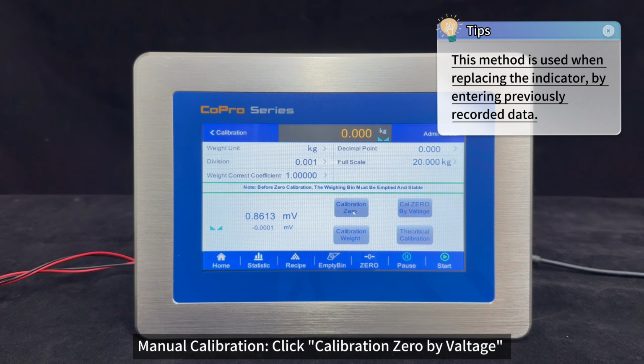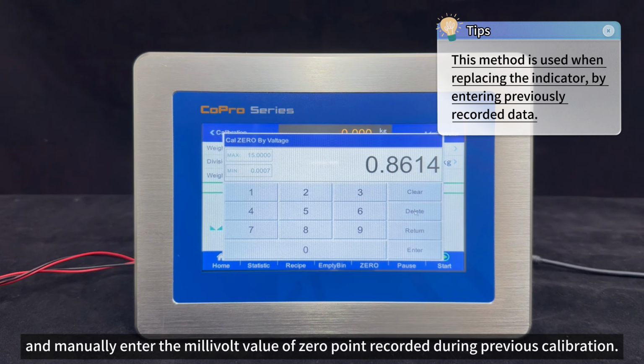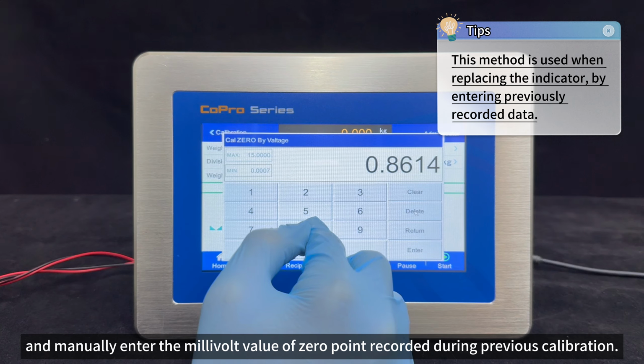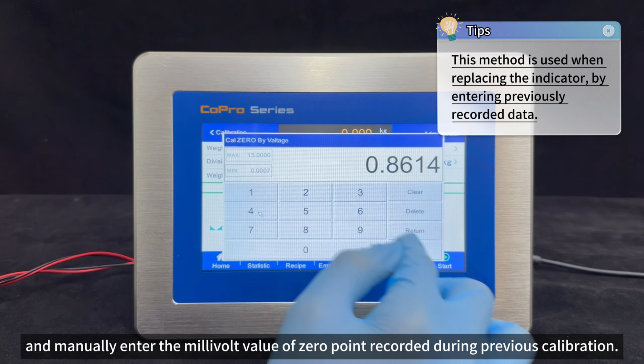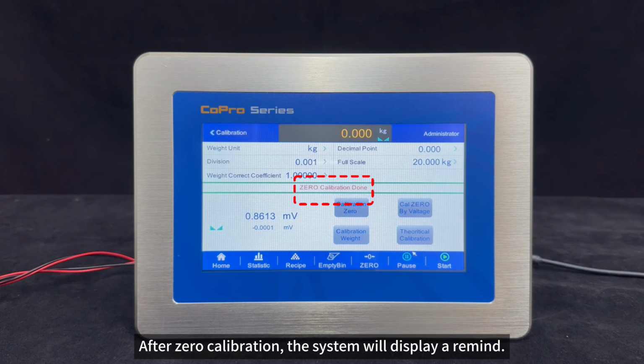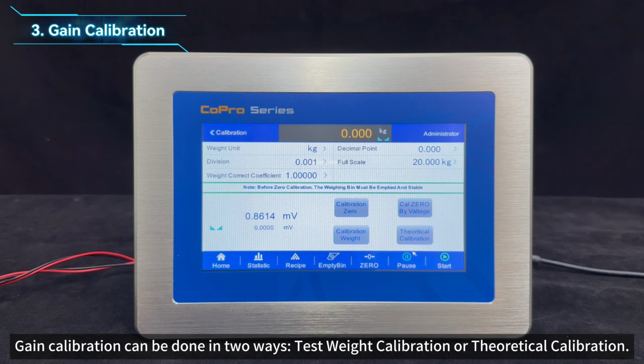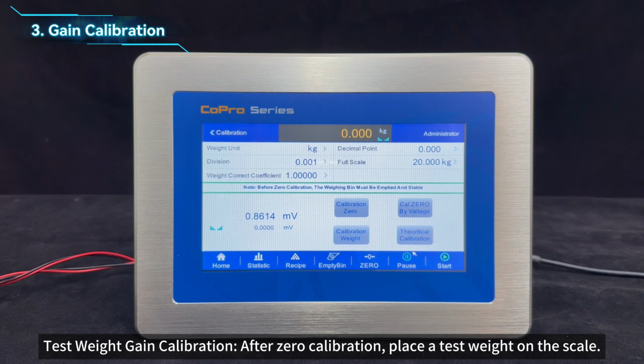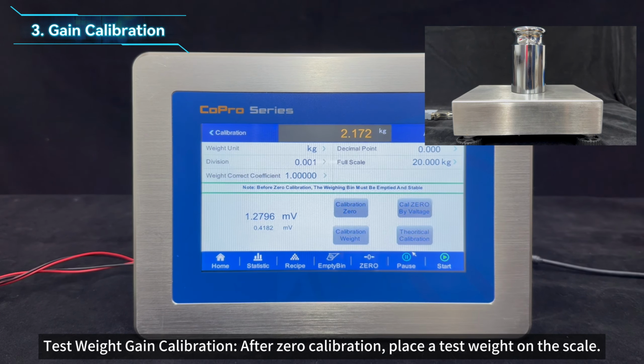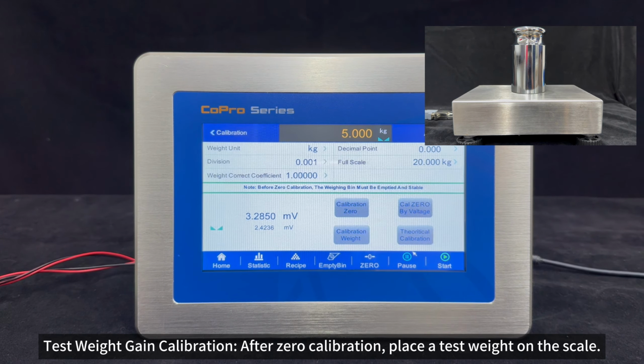Manual calibration. Click Calibration 0 by voltage and manually enter the millivolt value of 0 point recorded during previous calibration. After zero calibration, the system will display a remind. Gain calibration can be done in two ways: test weight calibration or theoretical calibration. Test weight gain calibration. After zero calibration, place a test weight on the scale.